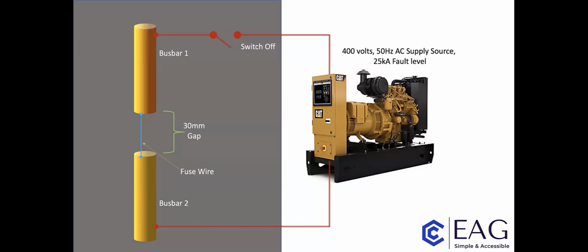As you can see in this diagram, there are two copper busbars facing each other across a 30mm air gap, connected to a 400-volt electrical source with a prospective short circuit capacity of 25,000 amps. I suppose it's the sort of output that you get from a 1000 kVA transformer, which tends to be pretty ubiquitous in industry nowadays. There's no protective device in circuit, only a switch. A piece of fuse wire connects the two busbars across that 30mm air gap.